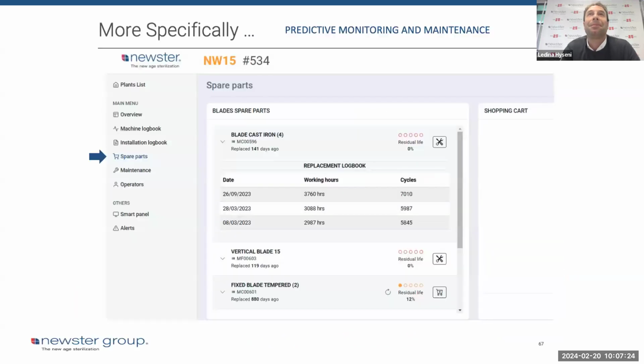As you can see, there are different parameters we can check, from the machine logbook where we register every cycle, to the installation logbook where we register and upload official documentation from when the machine is started up, including the commissioning test, the biological validation test, and the analysis we provide at startup. But now I would like to focus a bit more on the spare parts.